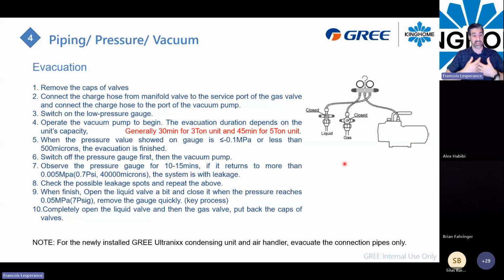If it's stable after 15 minutes, but you are in the range between 1,000 and 2,000 microns, and it's stable, the system is tight, you have no leak, but you have some sort of humidity in the system. If you are over 1,000, it's because you have some humidity in the system. If you can hold for 15 minutes somewhere between 500 and 1,000, the process is good and you don't have to vacuum more than that. If you hold it below 1,000, you're good to go.